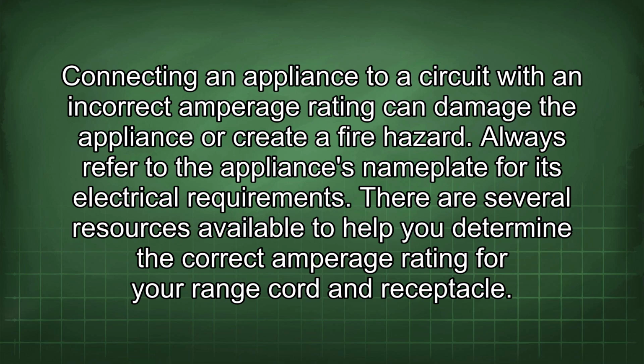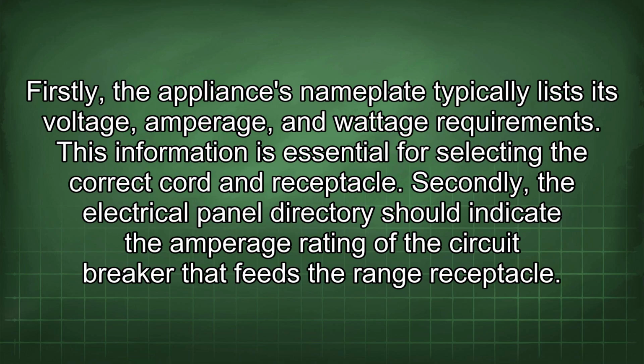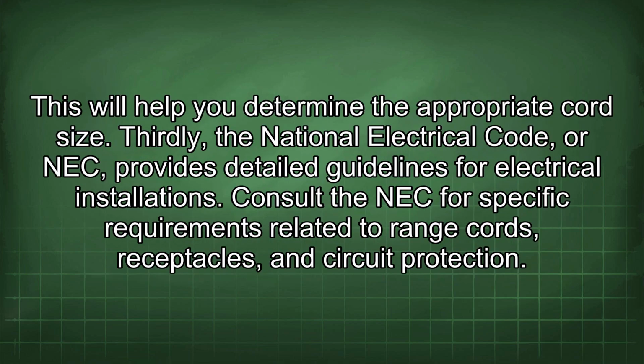There are several resources available to help you determine the correct amperage rating for your range cord and receptacle. Firstly, the appliance's nameplate typically lists its voltage, amperage, and wattage requirements. This information is essential for selecting the correct cord and receptacle. Secondly, the electrical panel directory should indicate the amperage rating of the circuit breaker that feeds the range receptacle. This will help you determine the appropriate cord size. Thirdly, the National Electrical Code, or NEC, provides detailed guidelines for electrical installations. Consult the NEC for specific requirements related to range cords, receptacles, and circuit protection.